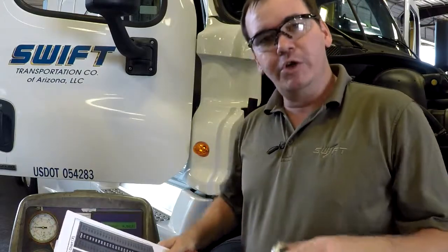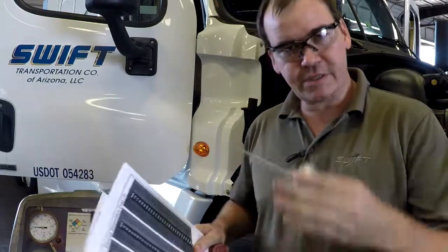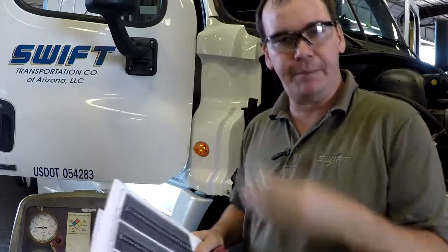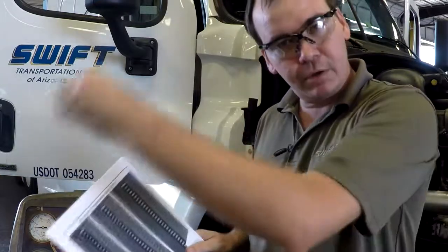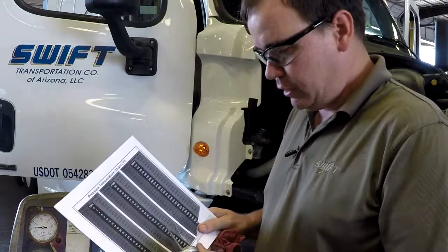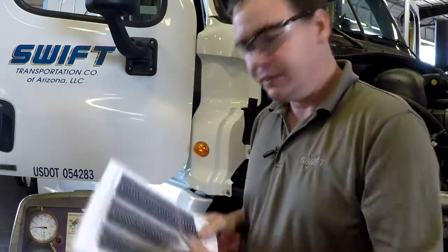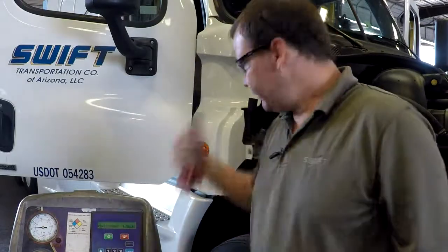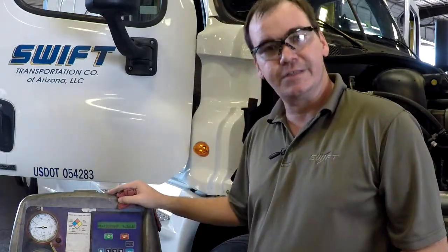But let's talk about what you do if it's below that. There is a leeway. You're allowed 10 psi above or 10 psi below. If it's 10 psi above that number or more, that indicates you have air or nitrogen in the system. So where it's supposed to be 105, if this was 115 or above, you would have NCG. You'd have nitrogen in the system or air or the wrong refrigerant. So what you do in that situation is go ahead and recover it and recharge it. This machine will take care of the NCG.